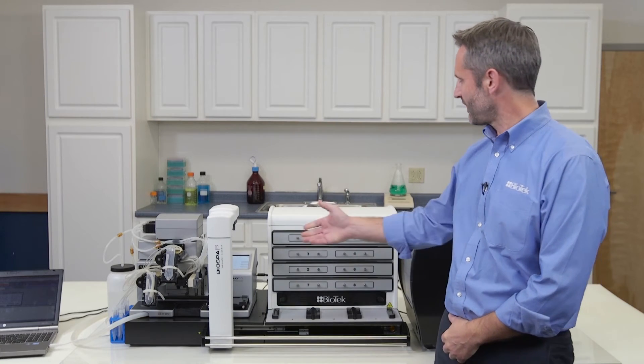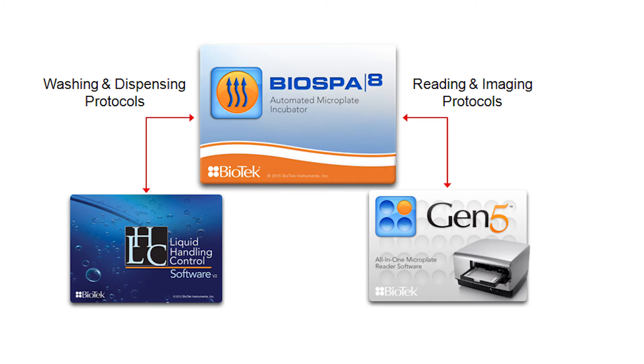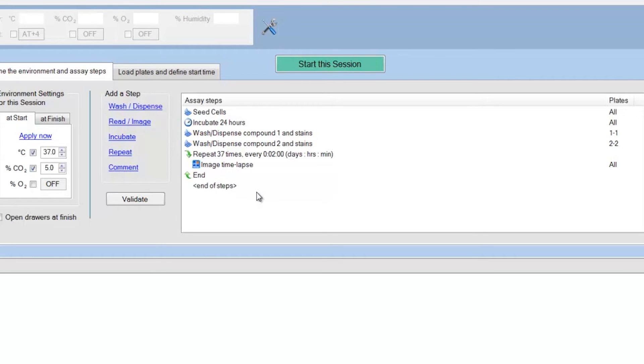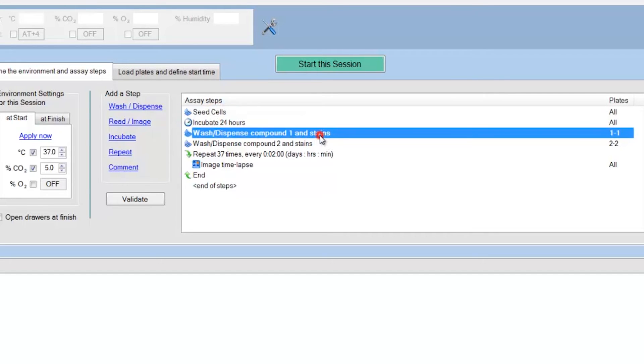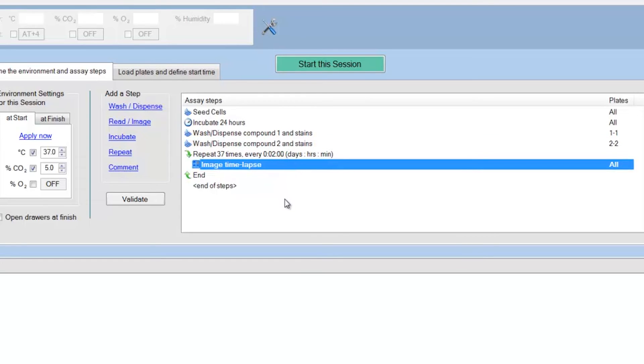BioSpa 8 interfaces with other devices through BioTek's existing software packages — Gen5 for readers and imagers and LHC for washers and dispensers. All you do with the BioSpa software is call existing protocols to create your workflow. What you see here on the right is a BioSpa workflow. Each of the three liquid handling steps I am highlighting calls a different pre-programmed protocol, and the final imaging step here just calls the same protocol multiple times to perform a time-lapse measurement. We will review this four-day workflow in more detail in the next video.